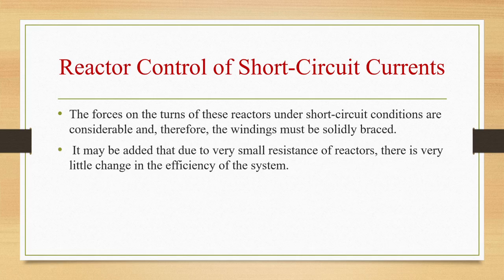The forces on the turns of these reactors under short circuit conditions are considerable, and therefore windings must be solidly braced. Here it can be added that due to the very small resistance of reactors, there is very little change in the efficiency of the system.